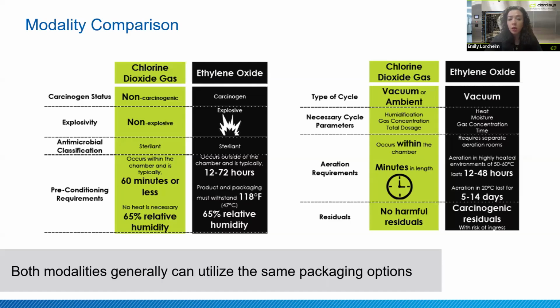The biggest difference, though, is the aeration phase. For a chlorine dioxide gas cycle, it's generally 30 minutes, varying by only a minute or two off of that 30 minutes. So very, very quick. It's conducted through only a series of vacuum exchanges within the chamber, whereas with an ethylene oxide cycle, this can be multiple days and often heated. Now, with residuals as well, chlorine dioxide gas has no harmful residuals, whereas ethylene oxide has carcinogenic residuals. So both are, again, good sterilants. Chlorine dioxide is a much quicker process, and both, considering packaging, can handle very similar packaging types.